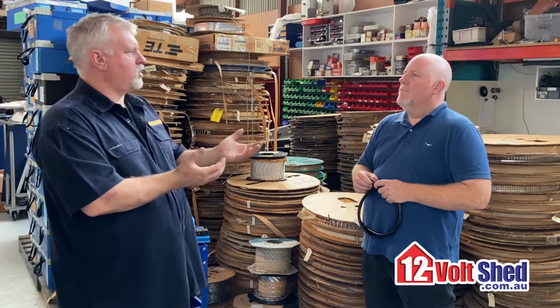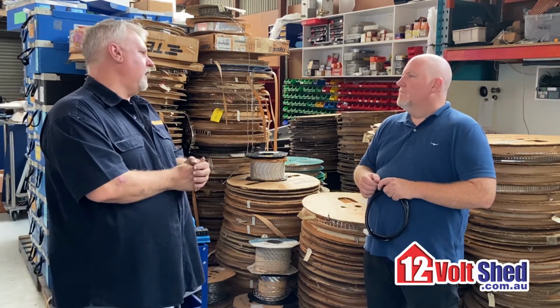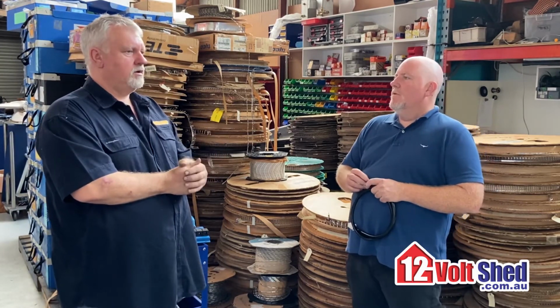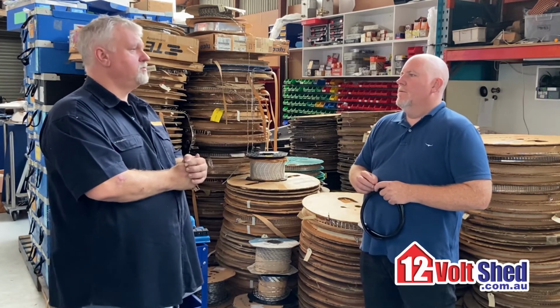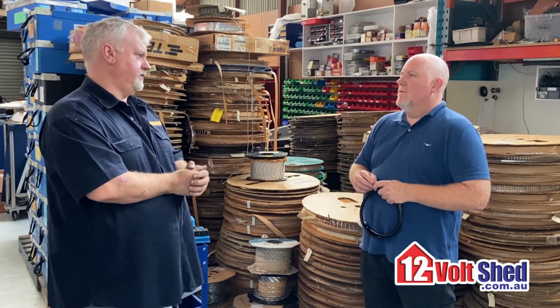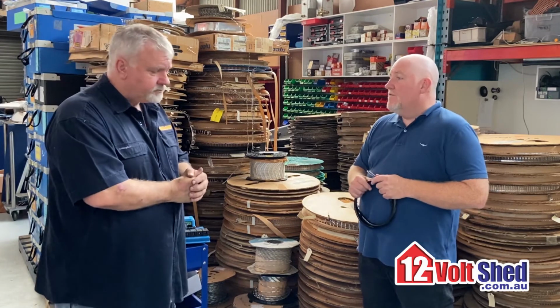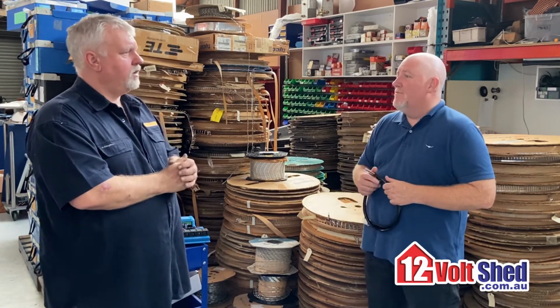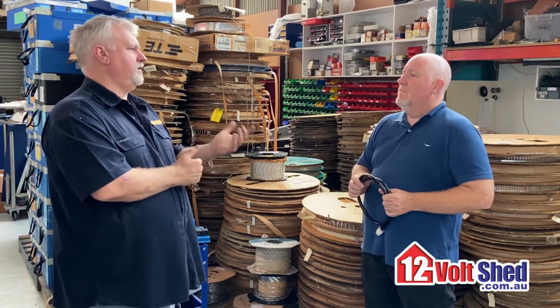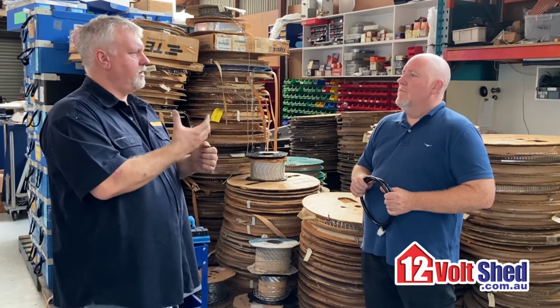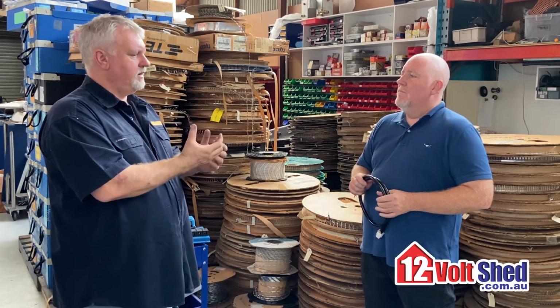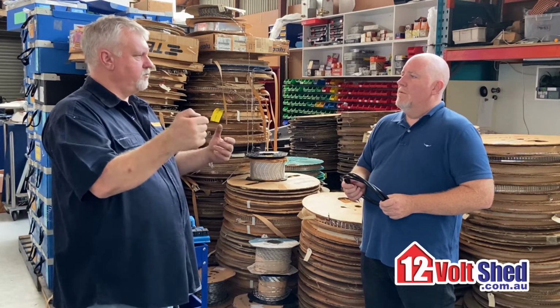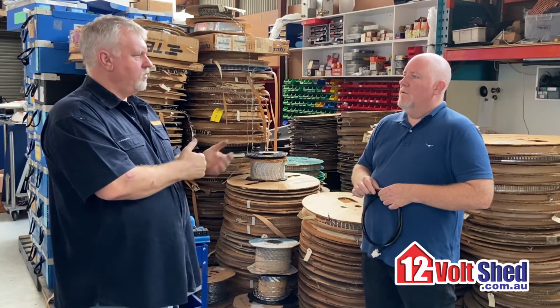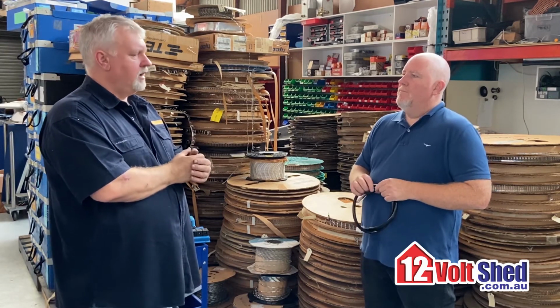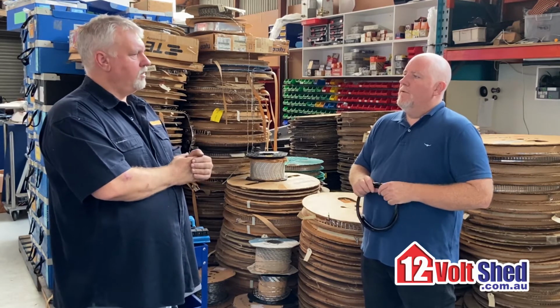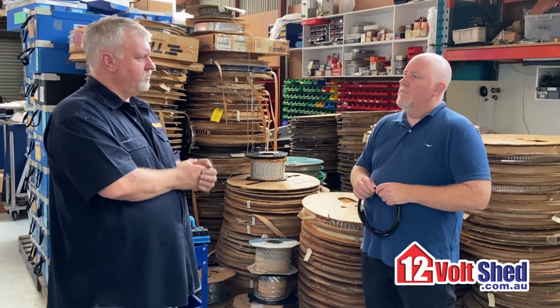So we're back to the common red, blue, yellow crimps. There's some really reasonably good ones out now that have got heat shrink tails on them. I've seen those, haven't used them myself, but I've seen a lot of the marine guys use them because they're very convenient. They crimp them on, heat it up, shrink it down, and it pretty much insulates the moisture from getting into the wire, whether it be tin, copper or not. They work quite well, but once again they're a little bit more expensive than normal crimps.